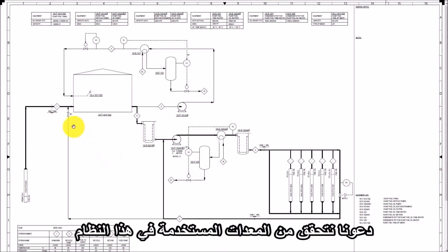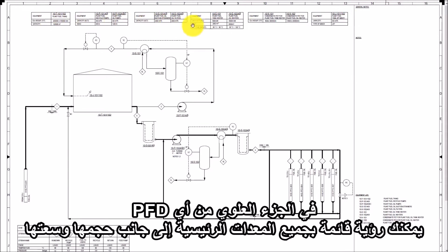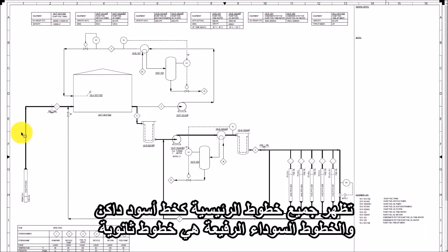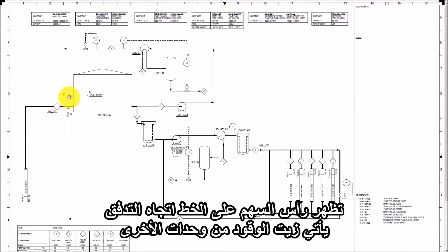Let's check the equipment used in this system. Here you can see the tank, pumps, exchanger, vessel, strainer, and jet mixer. On the top of any PFD you can see the list of all major equipment along with its size and capacity. All the main process lines are shown as dark black lines and thin black lines are minor process lines. Arrowheads on the lines show the direction of flow.